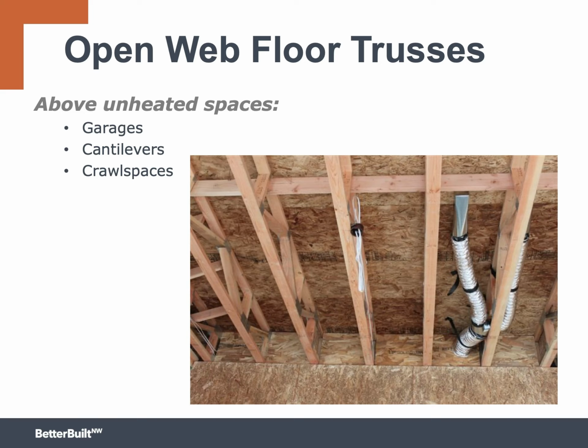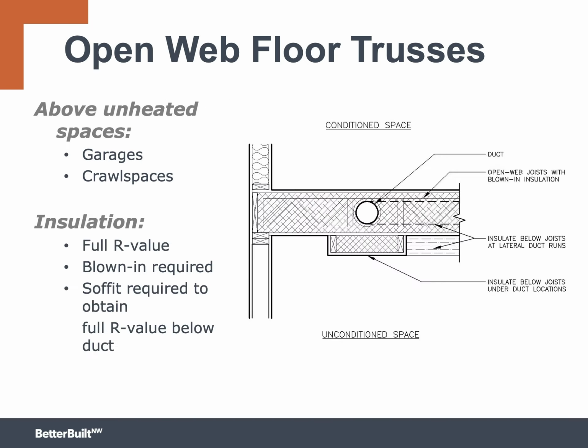Because the duct takes up most of the floor cavity, more framing has to be added below the duct to create additional space for insulation so that the insulation level there matches the insulation elsewhere in the floor. Here's a drawing that shows a little soffit below the duct to allow the same thickness of insulation to be installed below that duct as it is in the other parts of the floor. When ducts run through open web floor trusses over unconditioned spaces, they must be located as close to the subfloor and insulated with blow-in insulation.